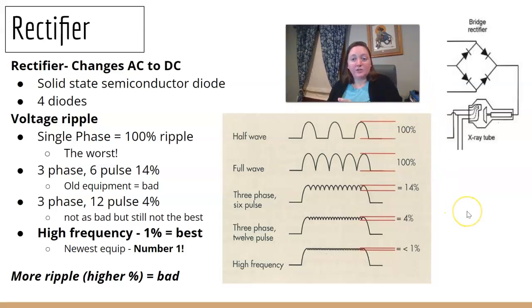Then, before we can hit our x-ray tube, we have to change our current from alternating current, which all three of the transformers work off of, to direct current. Our x-ray tube uses direct current. So we need something that's going to change that. And that's your rectifier. In some pictures, it looks like a diamond. And I think those are easier to identify. And they have the four triangles that are going to move it into one direction. So AC to DC. Sometimes these things are called solid state diodes. And you should have four of them. The rectification is either a half wave rectification or a full wave. So the half wave has the big open spaces here. We don't like that. Full wave. But I'm still getting a ripple here.